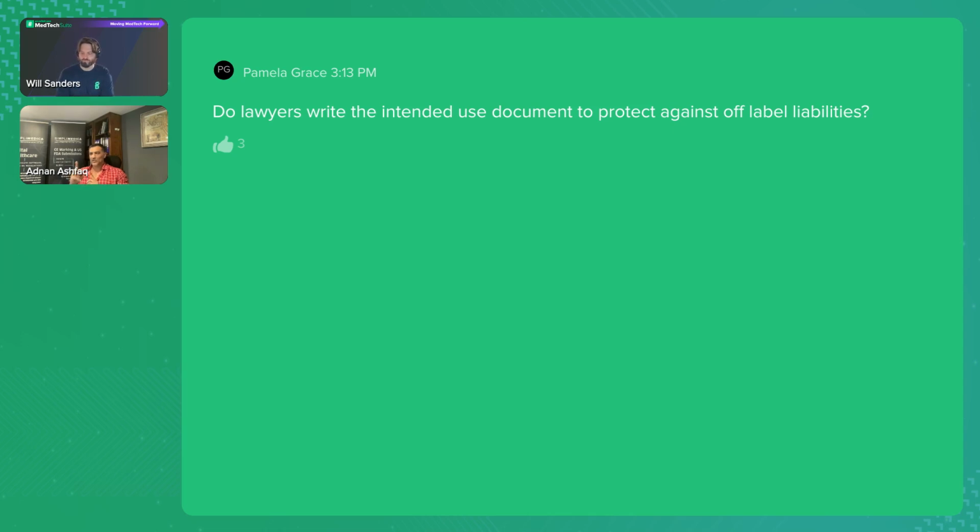This is why, when you have industry experience, you'll very often involve clinicians in your risk management who have that real-world experience, and they'll be able to tell you what really is likely to happen, what's reasonably foreseeable, and what's off-label. So the word of caution is to make sure you've got the right people with experience. Clinicians are key. Yes. And a lot of that factors into your ISO 14971 activities, where you look at probability of occurrence and things like that. All that comes together.